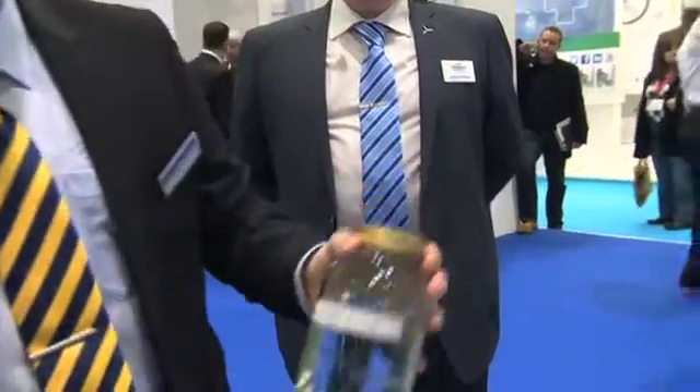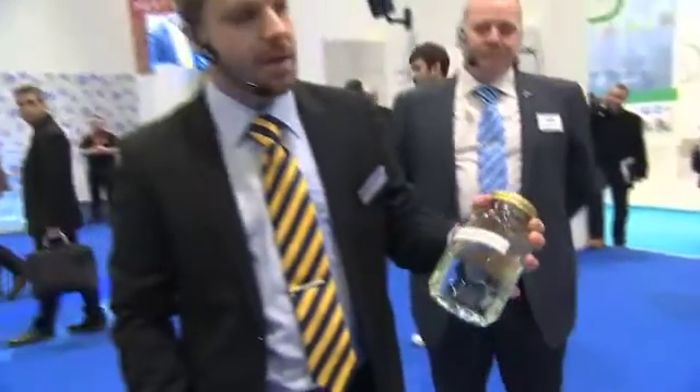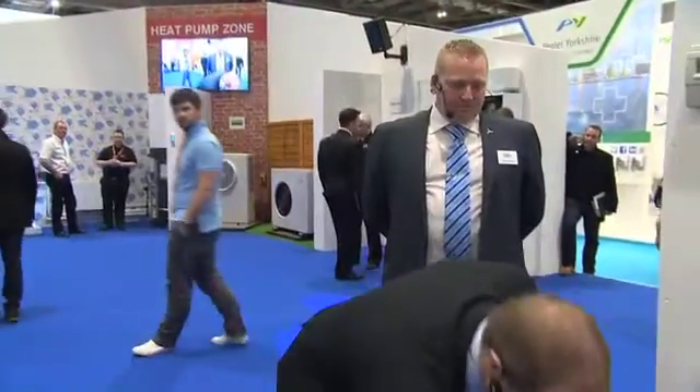In the Solar S1 that Fernox provides, we use a propylene glycol. It's a lot safer than ethylene glycol, and it provides frost protection. If you put it in the right dosage — which is already premixed in the Solar S1 — you get frost protection to around about minus 28 degrees C. So it is really good protection.